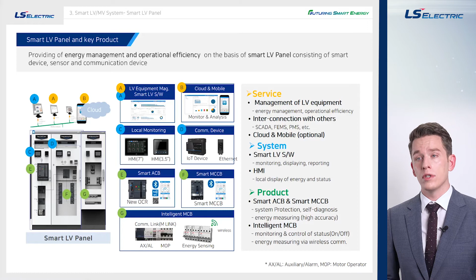Next, I will explain the smart MV panel configuration and key devices. First, in the product area, digital data is generated by sensors and smart devices such as intelligent VCB, IED, arc protection, thermal imaging camera, IR temperature sensor, and bus bar temperature sensors.